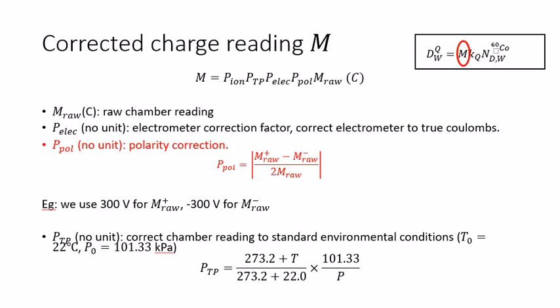The second factor is P-polarity, the polarity correction. Basically it corrects the subtle difference between biasing the chamber to the equal amount of positive and negative volts. This factor comes from our chamber measurement.